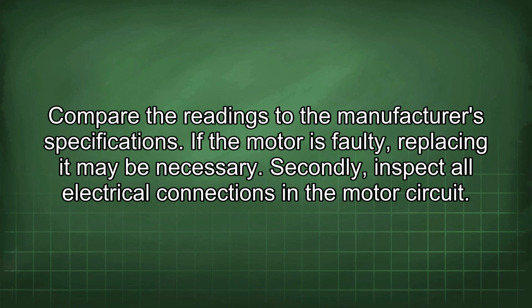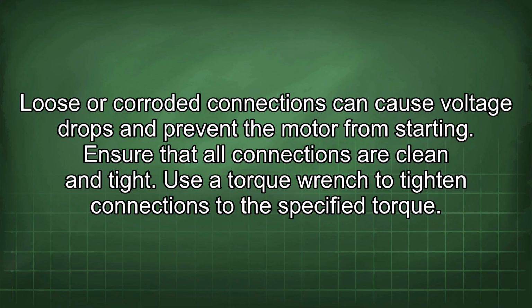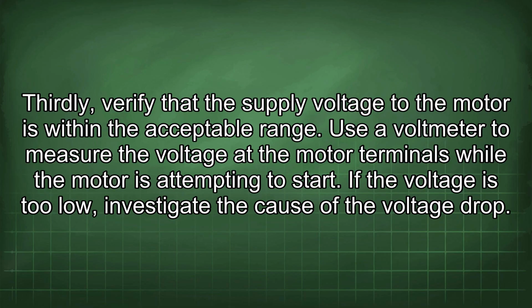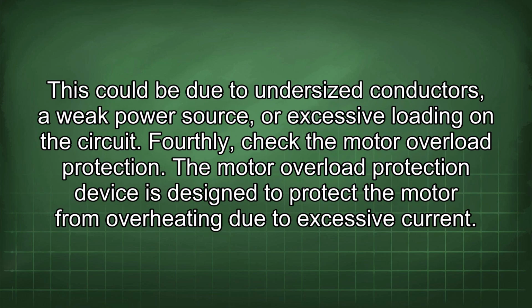Secondly, inspect all electrical connections in the motor circuit. Loose or corroded connections can cause voltage drops and prevent the motor from starting. Ensure that all connections are clean and tight. Use a torque wrench to tighten connections to the specified torque. Thirdly, verify that the supply voltage to the motor is within the acceptable range. Use a voltmeter to measure the voltage at the motor terminals while the motor is attempting to start. If the voltage is too low, investigate the cause of the voltage drop. This could be due to undersized conductors, a weak power source, or excessive loading on the circuit.